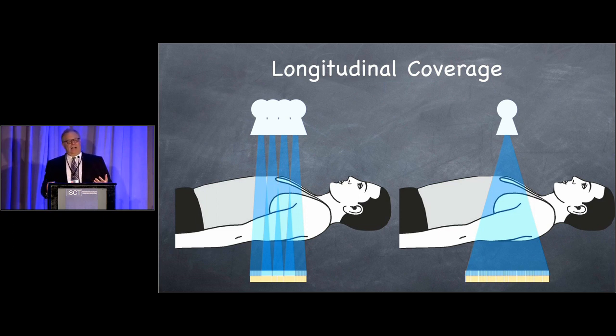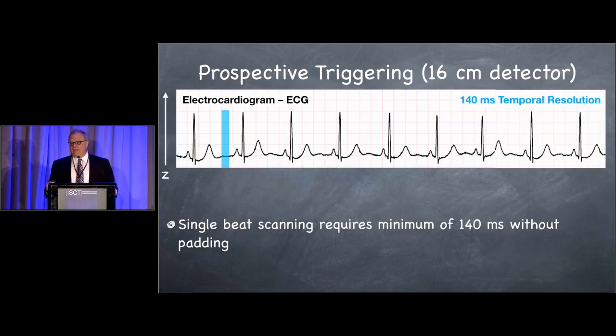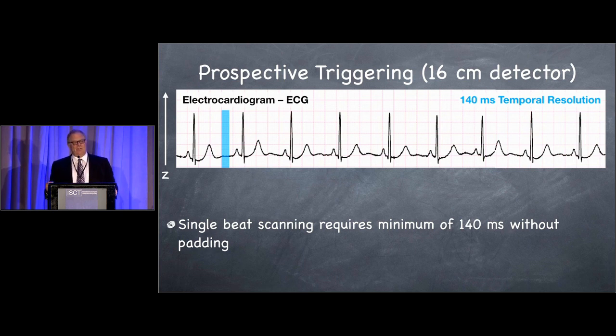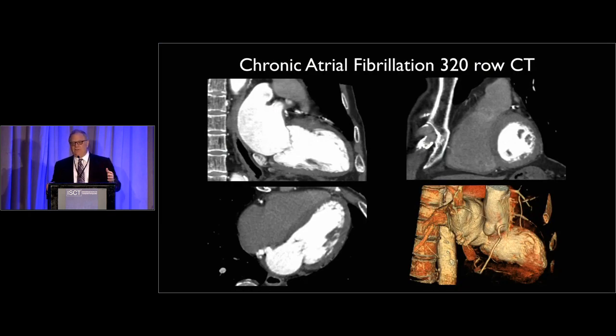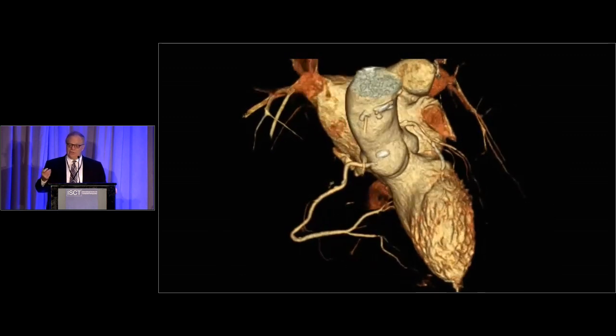The alternative to achieve high longitudinal coverage is to have a wide-area detector. With a wide-area detector, you can acquire your scan in a single beat, and that has a huge benefit because the scan duration in a 140 millisecond temporal resolution example is just 140 milliseconds. Here's a patient with chronic atrial fibrillation scanned on a 320-row scanner — even though there is an irregularly irregular heart rate, you see excellent clarity. You can also use these scanners to acquire a CINE acquisition of just one heartbeat playing over and over.